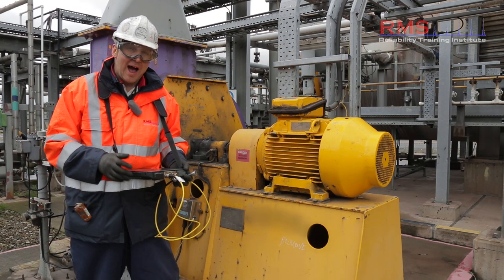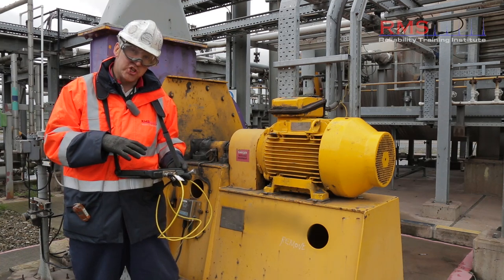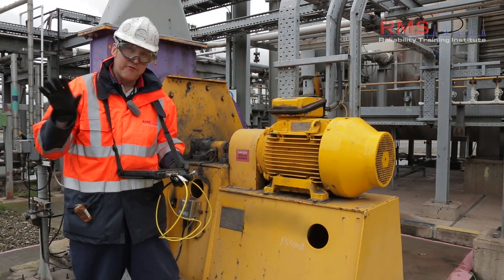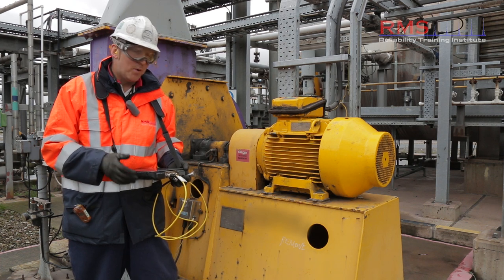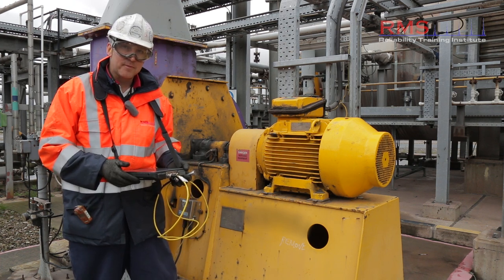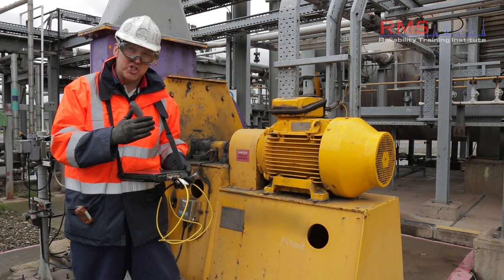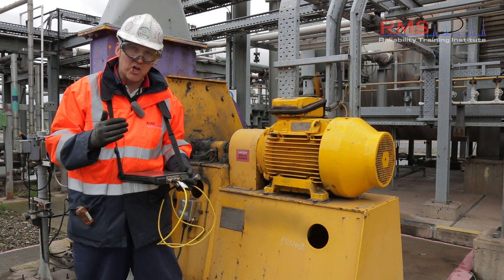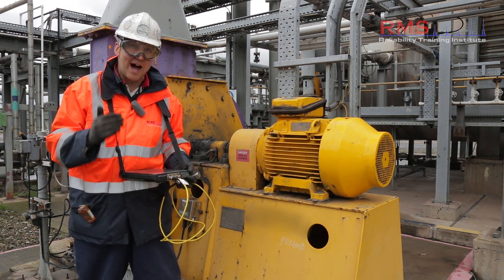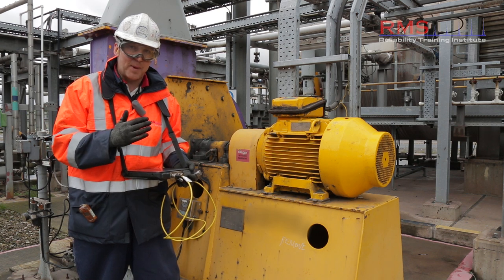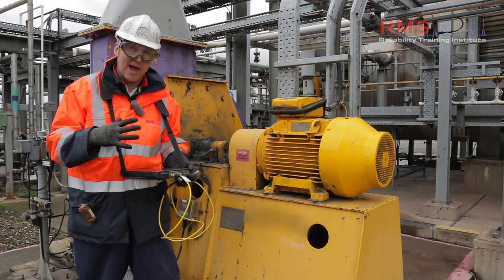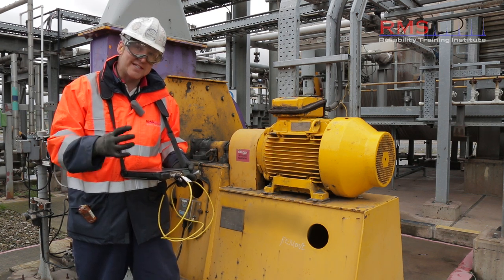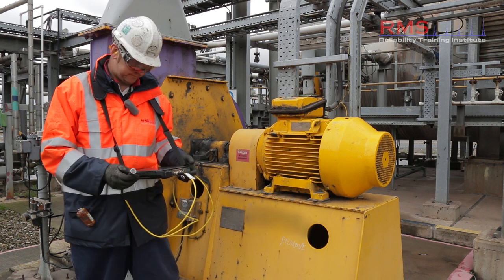Right, I've already loaded the vibration route into the analyzer from the software. We're now going to collect the data. It's a fixed speed machine, this. It's a two pole motor running at 2980 RPM. So I know my speed, I've set it up in the database, I've got a good setup, let's collect the data.